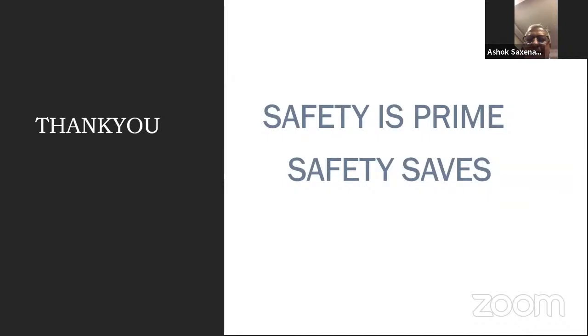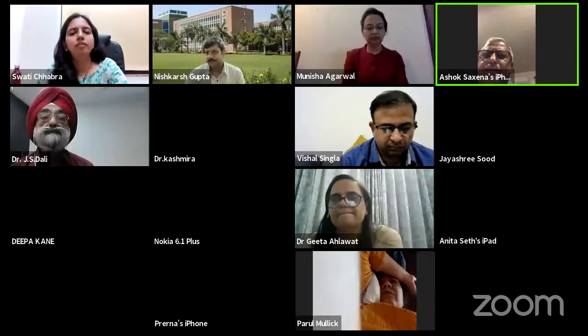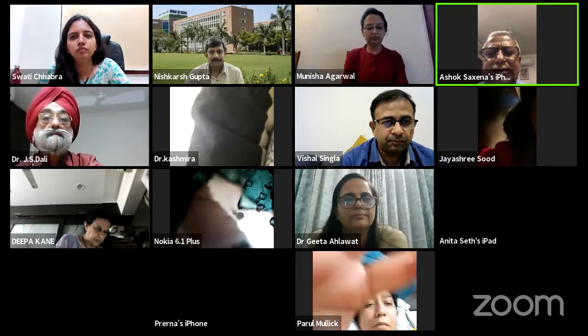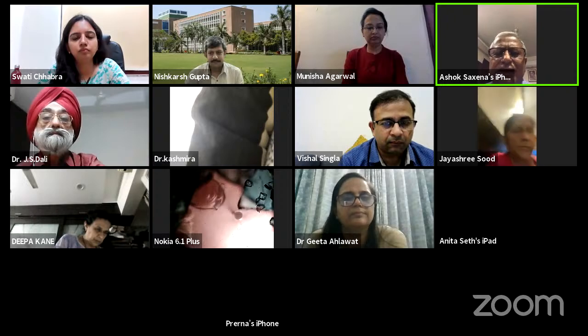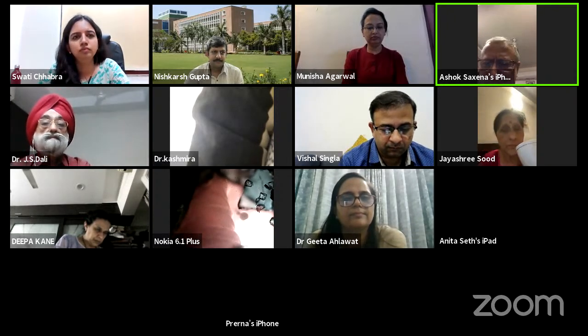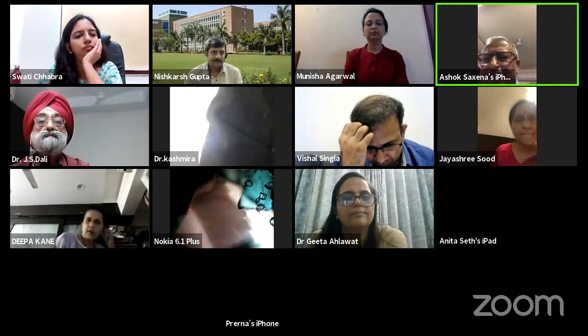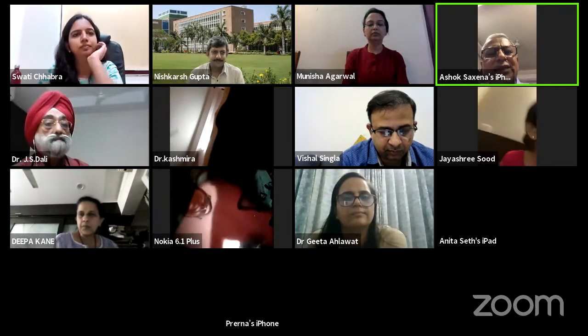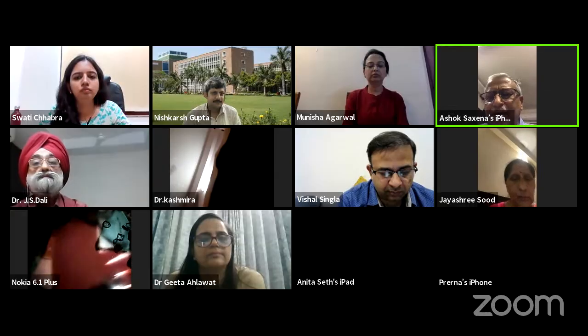Geeta. Thanks for a wonderful talk, right from the most basic aspects to the advanced and the modern versions. And in the modern times, as our young budding anesthesiologists are, you really summarized everything so quickly and so enormously that everything was really beautifully touched upon. And I'm sure we are going to have questions right in the end. That's what we have decided. And you wonderfully talked about when exactly you are going to get your nitrous oxide shut off. If we talk about the modern anesthesia machines and the workstations, if the oxygen flow is less than 200 ml per minute, or if the oxygen fresh gas valve is closed, definitely the nitrous oxide supply is cut off. You very beautifully summarized that.